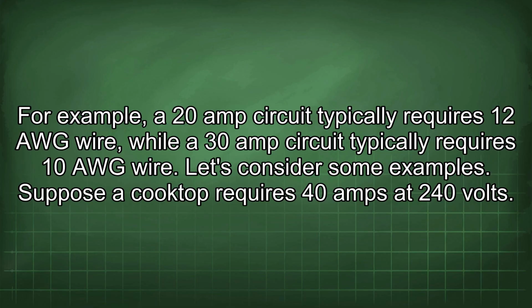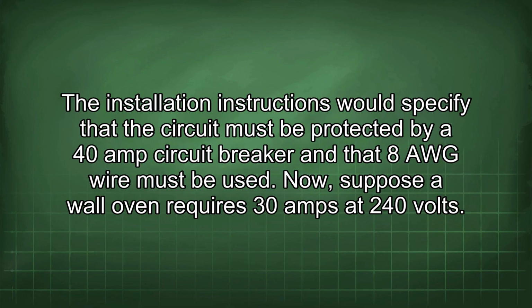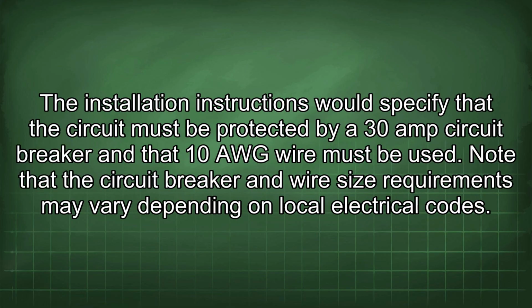Suppose a cooktop requires 40 amps at 240 volts. The installation instructions would specify that the circuit must be protected by a 40 amp circuit breaker and that 8 AWG wire must be used. Now, suppose a wall oven requires 30 amps at 240 volts. The installation instructions would specify that the circuit must be protected by a 30 amp circuit breaker and that 10 AWG wire must be used. Note that the circuit breaker and wire size requirements may vary depending on local electrical codes.